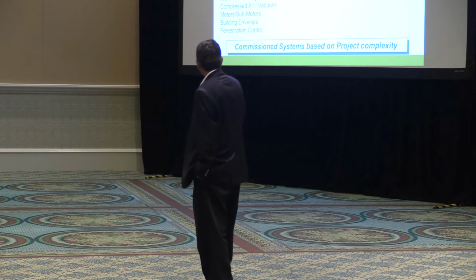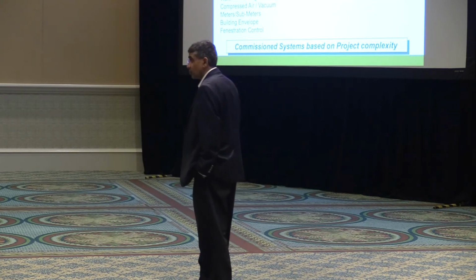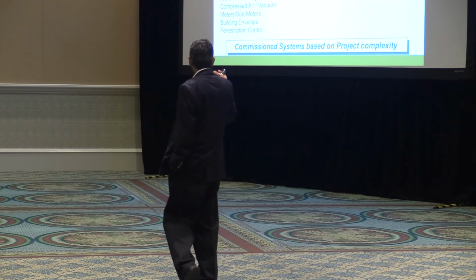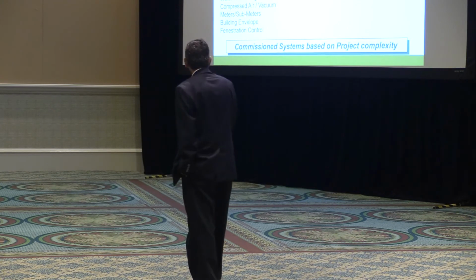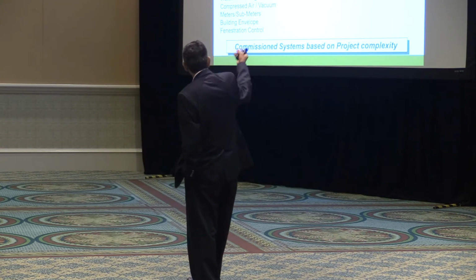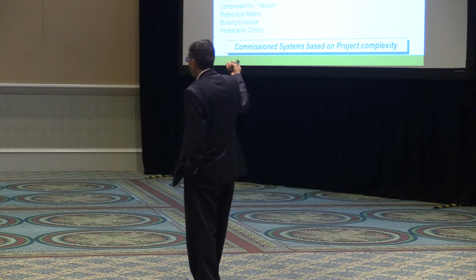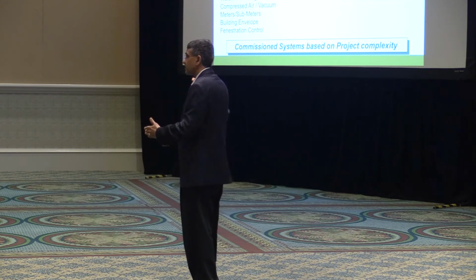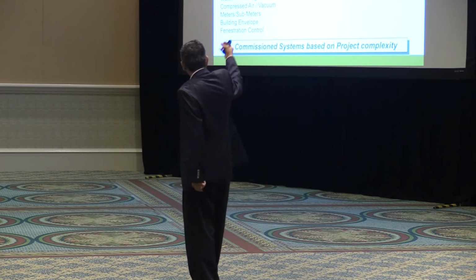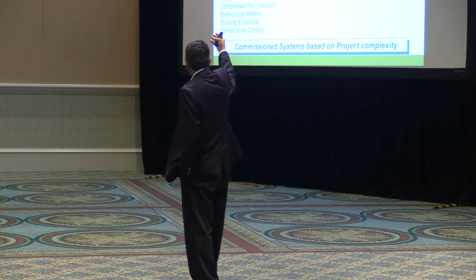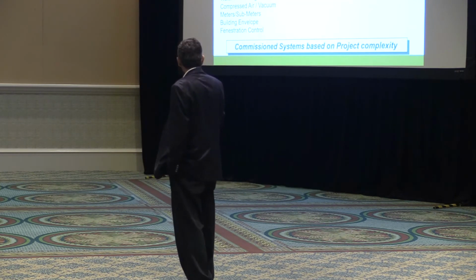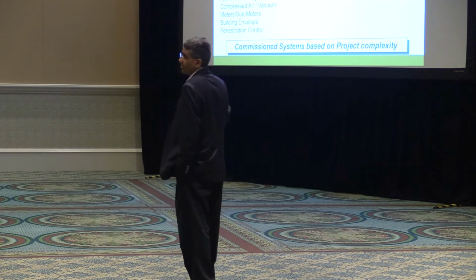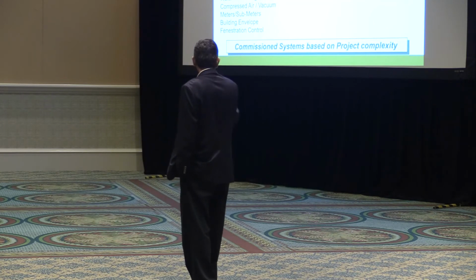One of them is UFC 1-200-02, the high performance sustainable building requirements, which is based on IGCC and IECC. We look at the project size and type of documents, and based on this, define what systems need to be commissioned, then introduce that into the commissioning spec.